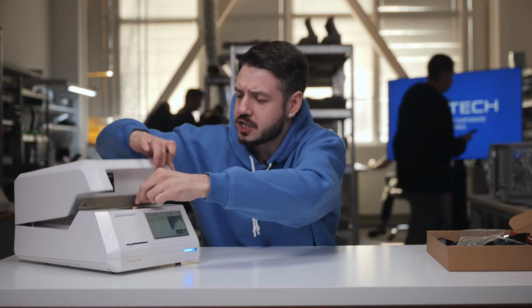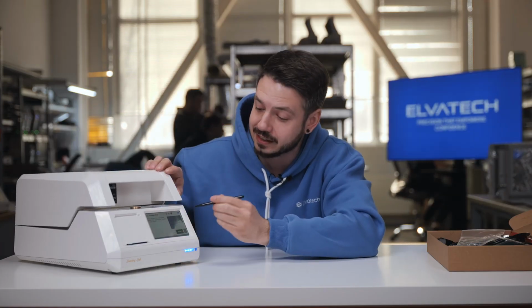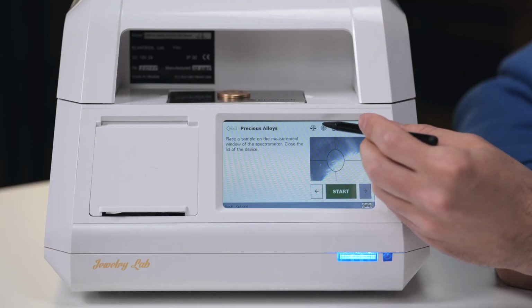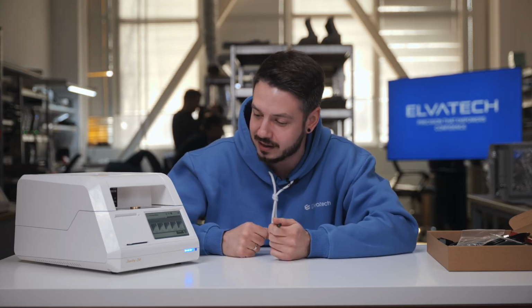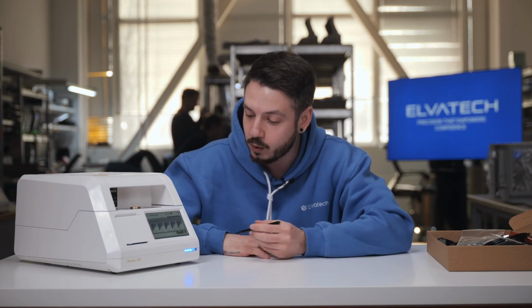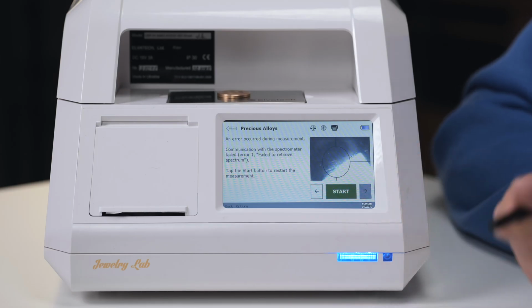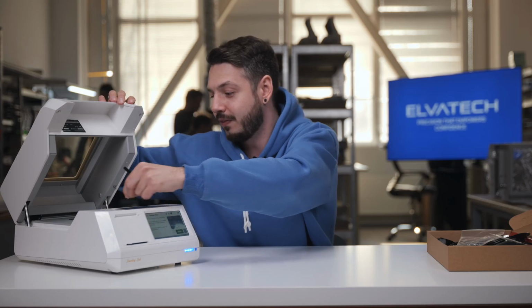And then let's position it. Oh no, first of all, we can actually set our collimators here with the sample, and on this exact device we have 5 different sizes of collimators, and I think as our sample will just cover all the measurement window area, we can stick with the biggest one, which is 6.5 millimeters in diameter. So next step is to position our sample as we are totally ready for the measurement. And as soon as you put the lid back, the device starts measuring itself. But you actually can change the settings and it will measure only when you press the start button. And we finally get the result. So let's check it out.